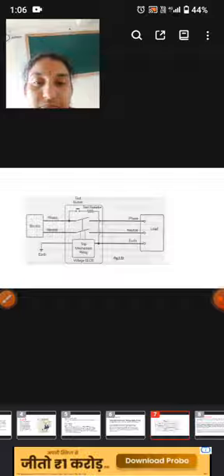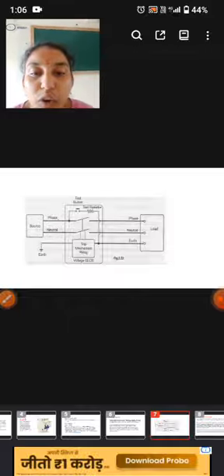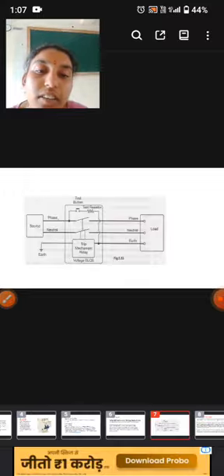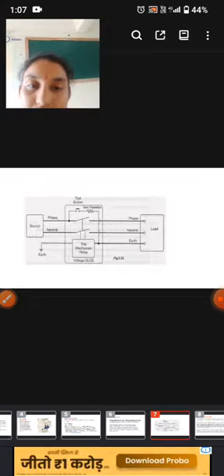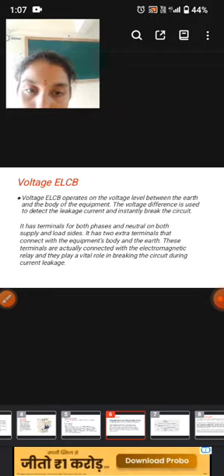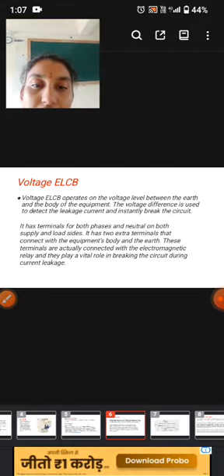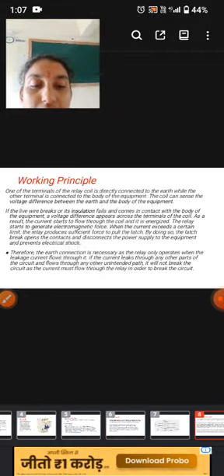This is the diagram of voltage ELCB, where phase and neutral are connected to the source, and in the load there are three terminals: phase, neutral and earth. Earth is connected to the load for the electromagnetic relay, and it plays a vital role in it.